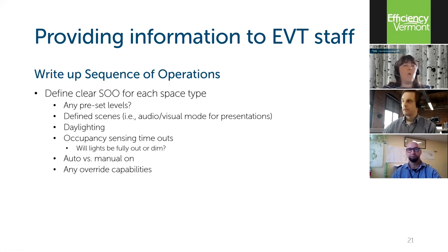As we're doing that, you're going to want to write up a sequence of operation: any preset levels, defined scenes for audio visual presentations, conference rooms, classrooms, what the daylighting looks like, which fixtures get daylighting, which only have occupancy, and what the timeout is, whether 30 seconds, 2 minutes, or half an hour. Are they auto on or manual on? Any override capabilities? Let's figure these out and write it all out ahead of time, so when they're installed we have everything figured out.